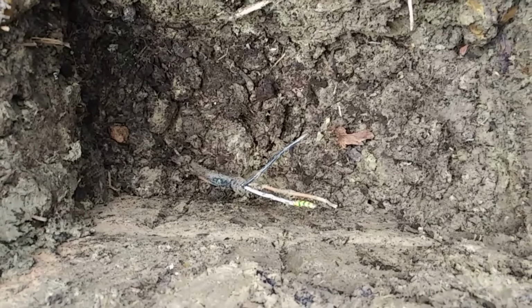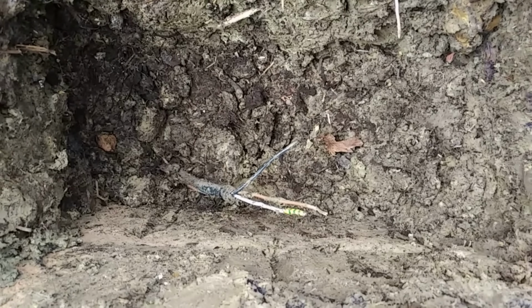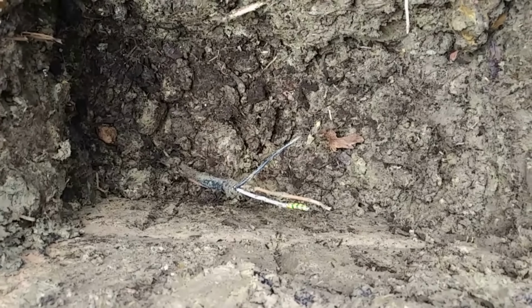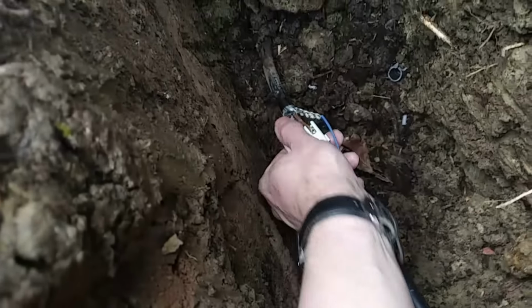Like I say, this is a 2.5mm. I've bought an RCBO that's at 20 amp. We're going to run the circuit at 20 amp now. I'm actually going to splice in the 6mm because I've got 6mm SWA on the van. The section that's going through there will improve the earth fault loop impedance and voltage drop, very slightly, for what it's worth.